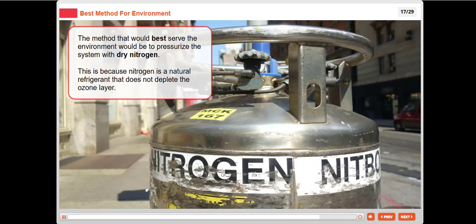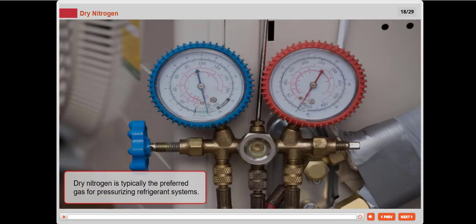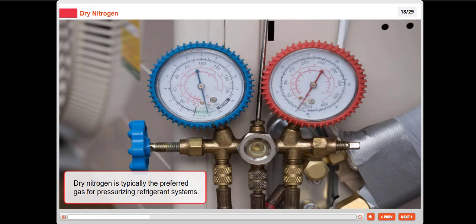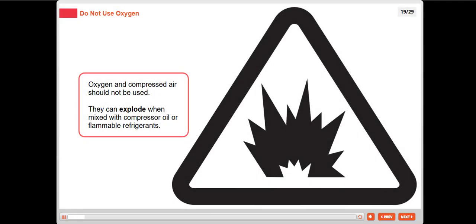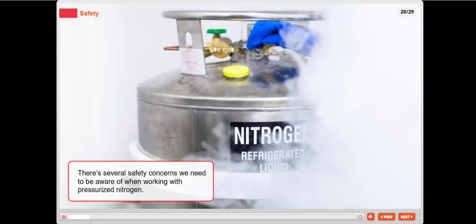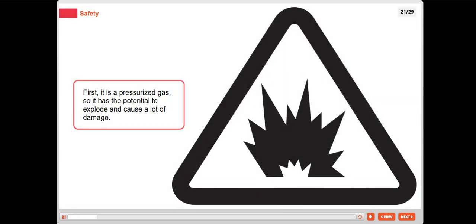Dry nitrogen is typically the preferred gas for pressurizing refrigerant systems. Oxygen and compressed air should not be used. They can explode when mixed with compressor oil or flammable refrigerants. There are several safety concerns we need to be aware of when working with pressurized nitrogen. First, it is a pressurized gas, so it has the potential to explode and cause a lot of damage.